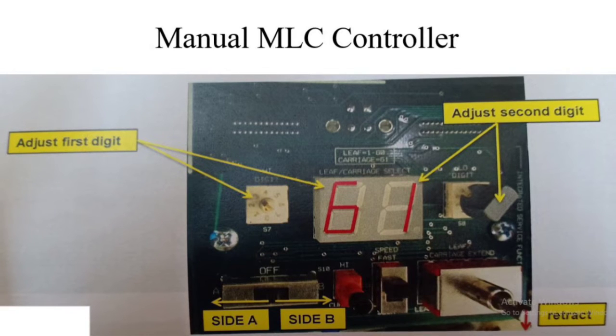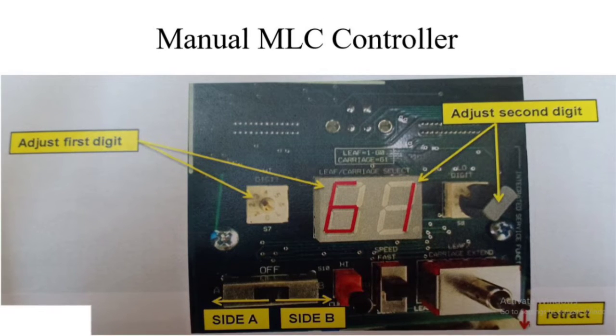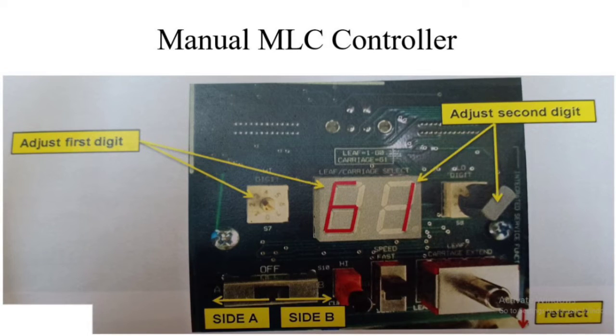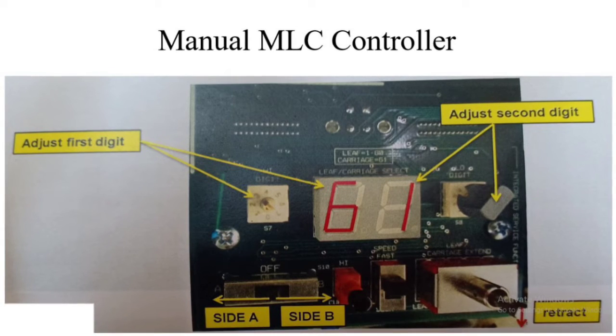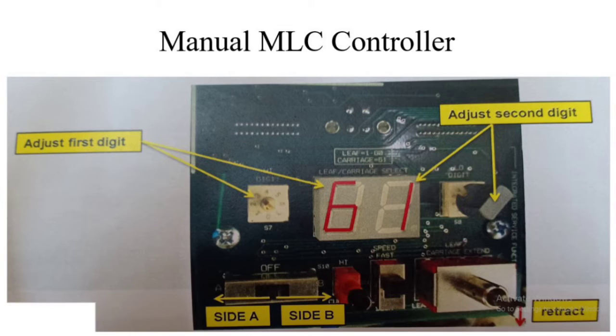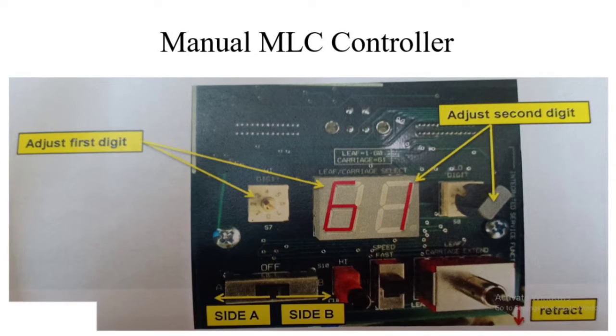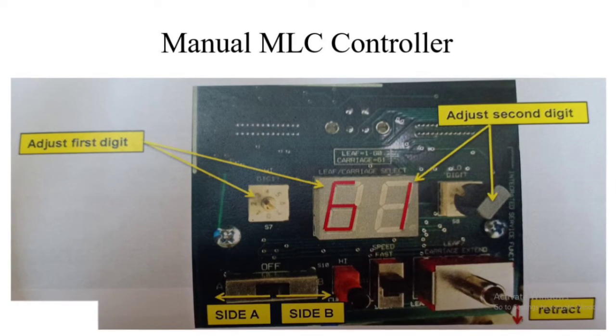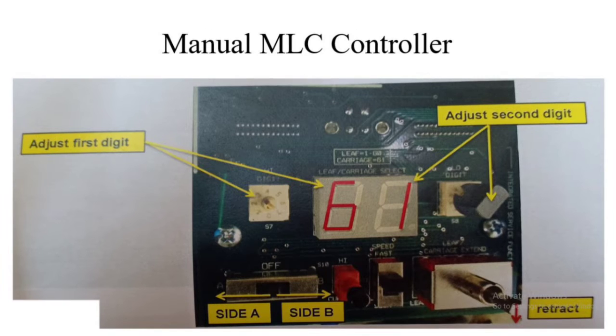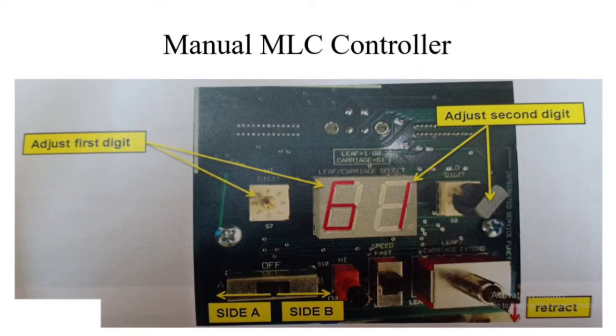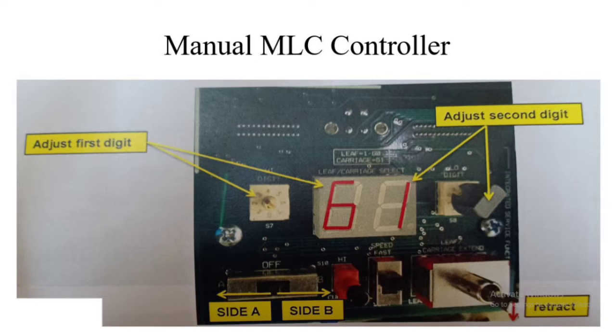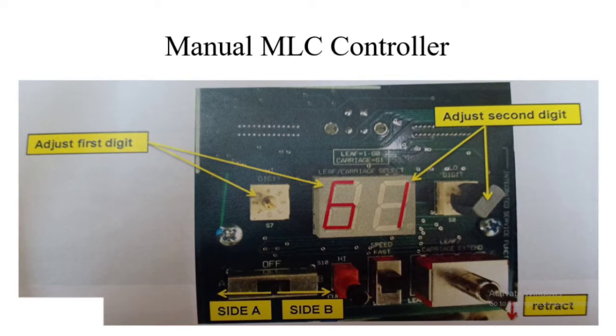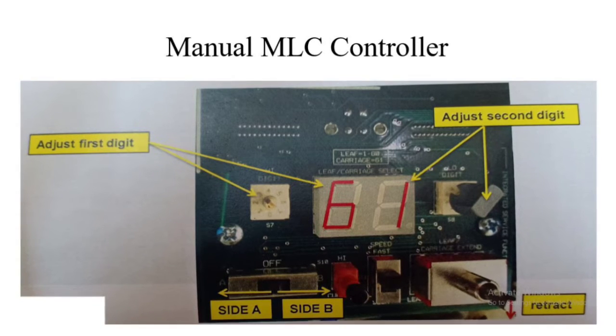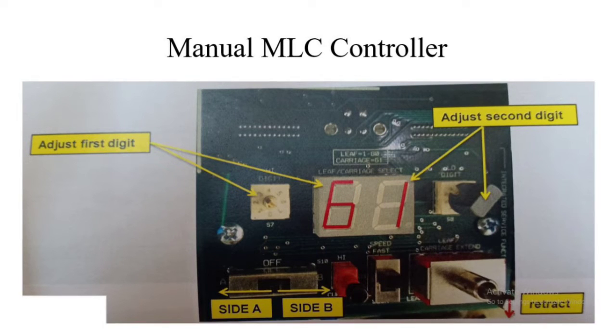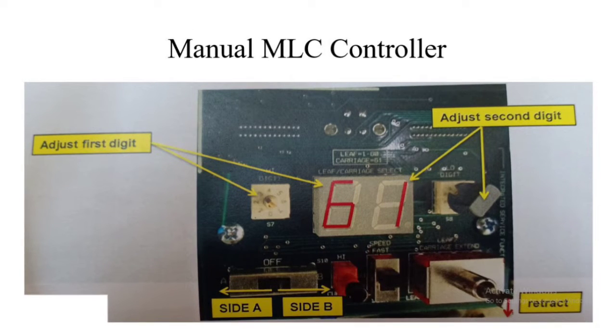From here on, there is going to be a two-step investigation. First, you have to move the MLC manually. If the leaf is moving manually, then you are supposed to change the motor. However, just performing the MLC initialization might fix the issue for a time, but the same MLC leaf stuck would occur in the future. The second case is if the leaf is not moving and it has a free in-and-out motion when you dab the leaf by finger, then most probably there is a T-nut problem. Now we will see how to replace the MLC motor.